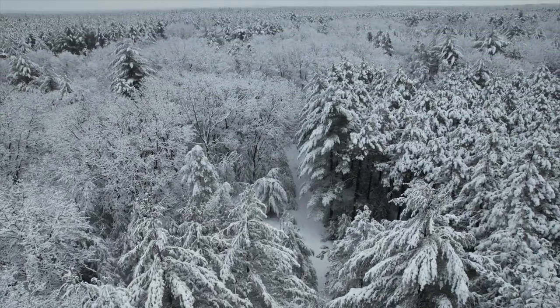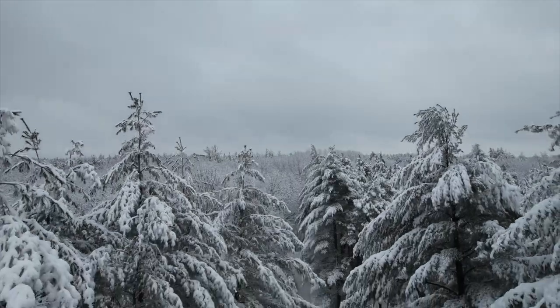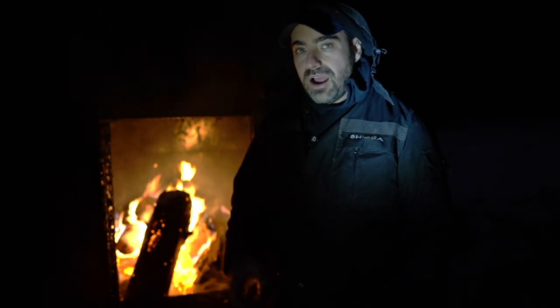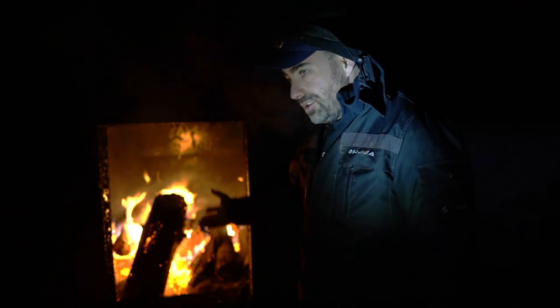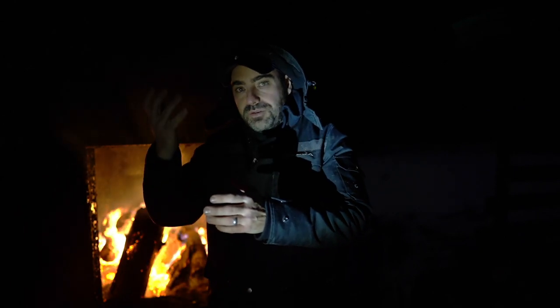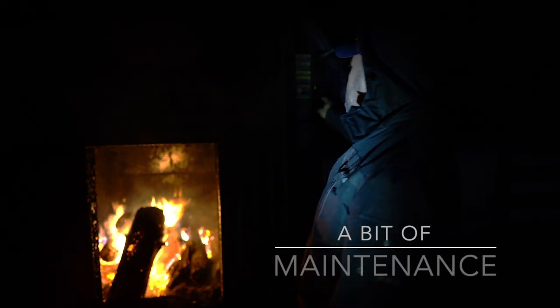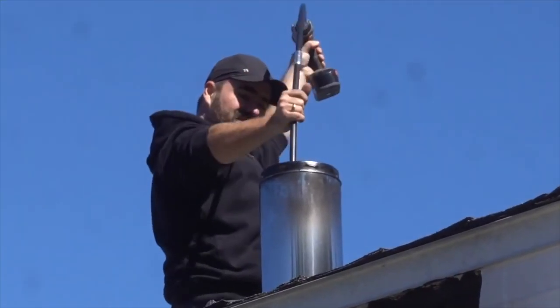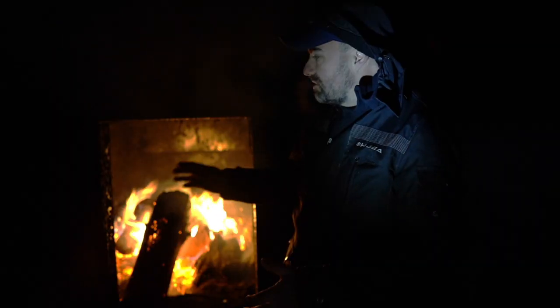This is the CL6048 from Central Boiler — again, it's before the energy-efficient models came out. We load this thing up to the top and it'll go almost 24 hours depending on the temperature and the wood. It's a huge firebox — you can put full rounds in here so we can really load it up and kind of forget about it. One question I get a lot: is there water or antifreeze in it? We have water in ours. Antifreeze is very expensive, and the odds of this liquid freezing are very low because it's either running or, if we go on vacation for a week, I just leave the furnace on — it pumps the water through the coil and the propane keeps it from freezing. There's a temperature gauge on the side and a water level indicator. You want to maintain these really well: keep the door clean, change the gasket.